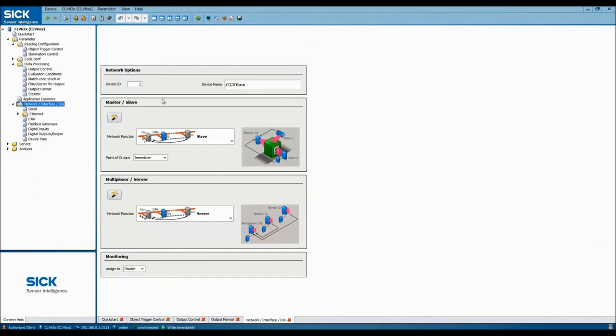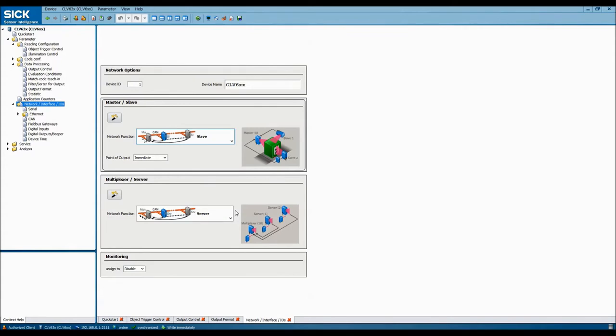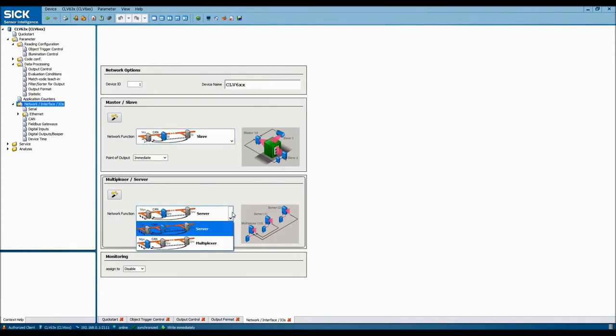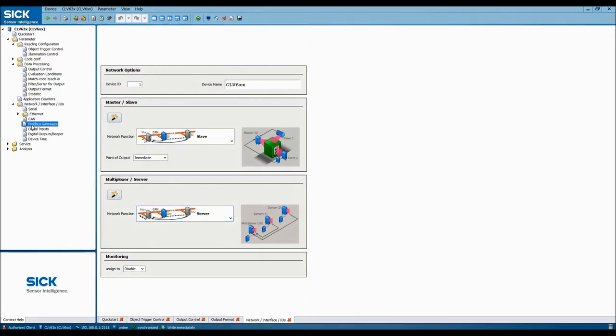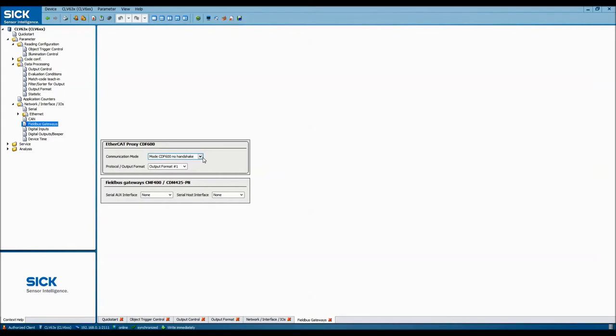Now we need to tell the scanner how it is set up in the network. For this application, we need to make it a slave so that the PAC can control what to do with the data. We'll select an immediate point of output, and we'll set it up as a server as opposed to a multiplexer. For the field bus gateway, set the communication mode to CDF600, no handshaking, and the output format to output format 1, which is the format that we created earlier.